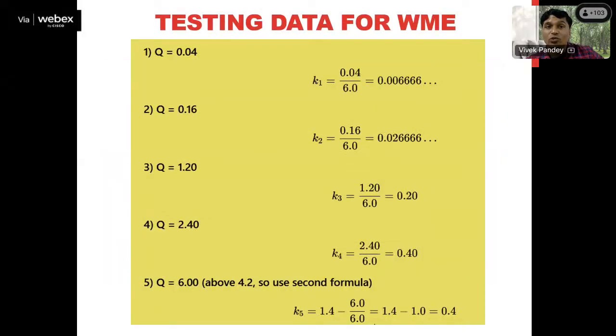When we use these values, suppose the Q value is 0.04, then K1 will be 0.04 upon 6. You can see what formula we are using here: Qi upon Qmax. Why? Because in this case the flow rate is less than 0.7 of Q maximum. But if you go to the last flow rate, when Q was 6 meter cube per hour, that is the maximum flow rate.